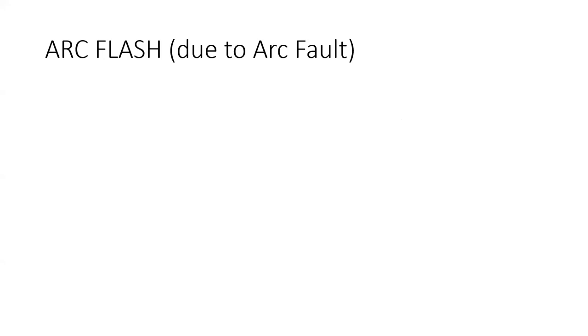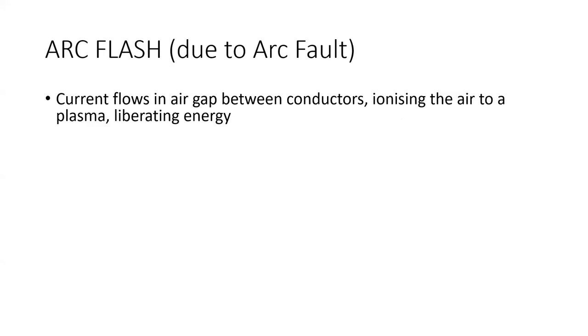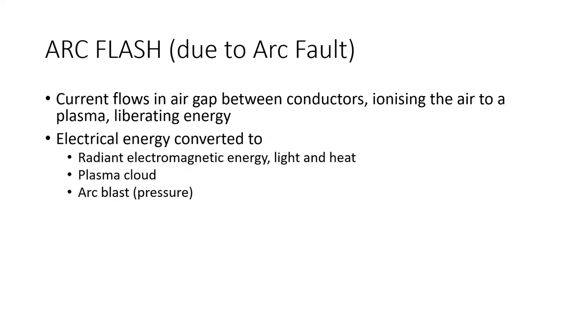So just briefly recapping on arc flash, what are some of the features of an arc flash? An arc flash is when current flows in an air gap between conductors. The air ionizes, which means it starts conducting. The air becomes a plasma and it liberates a heap of energy. And that energy can be classified as radiant energy, which is heat and light, right throughout the electromagnetic spectrum from radio waves all the way up to x-rays.